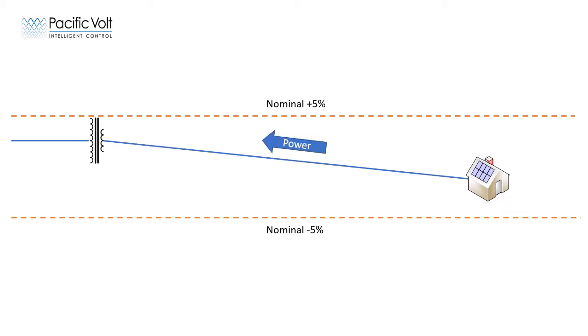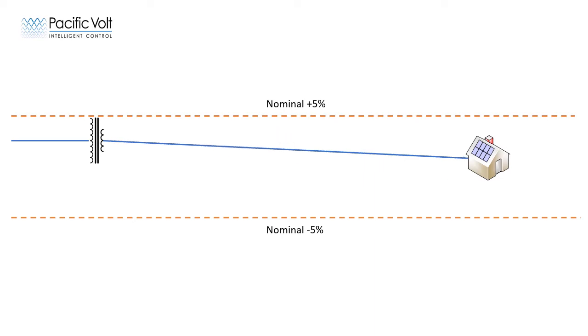The same impedance or resistance that causes the voltage to drop when energy is consumed also prevents the solar inverter from pushing the energy back through the transformer onto the medium voltage feeder. As more of the building's energy is supplied by the solar, the voltage at the building will begin to rise. This is because the amount of power supplied from the grid is being reduced or offset by the solar energy.